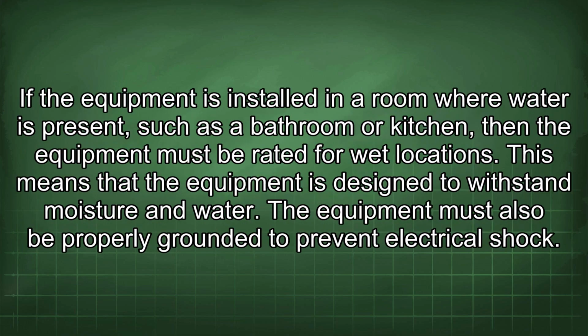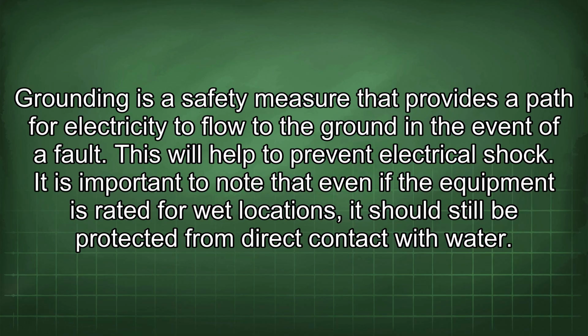If the equipment is installed in a room where water is present, such as a bathroom or kitchen, then the equipment must be rated for wet locations. This means that the equipment is designed to withstand moisture and water. The equipment must also be properly grounded to prevent electrical shock. Grounding is a safety measure that provides a path for electricity to flow to the ground in the event of a fault. This will help to prevent electrical shock.